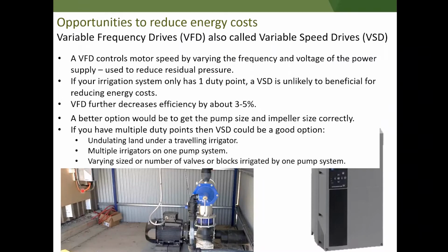Where a VSD is really useful is where we've got multiple duty points. So if you've got undulating land, as the travelling irrigator moves over the land, as it irrigates higher land, the pressure it has to push against will increase. And so a VFD could be useful in reducing energy costs there. I'd say in most cases, there's probably not enough undulation in northern Victoria where we are, but other areas could well have it. If you've got multiple irrigators working off one pumping system, then certainly a VFD will be useful, and we'll have a look at an example of that. And in horticulture, where you've got varying sized or numbers of valves that you might be irrigating at different times off one pumping system, then having a VFD in that situation can really reduce energy costs.